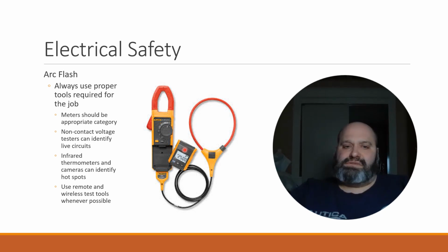The multimeter that I use, and that most of you use, you've got to stand there with it to take your readings. Well, with this one, you can put the hoop around the conductor, remove the faceplate, and go into the next room or behind a protective barrier so that when you power on the machine, you can get your amp reading without actually being right there.